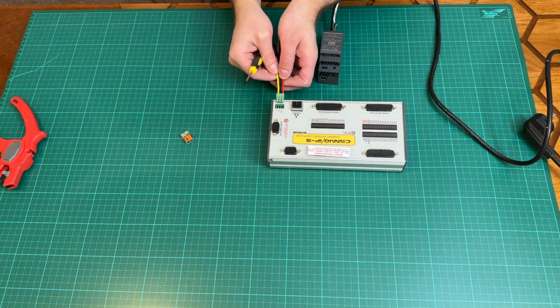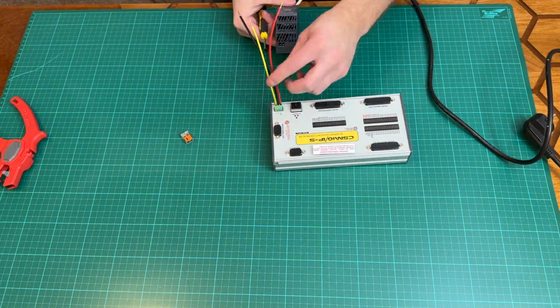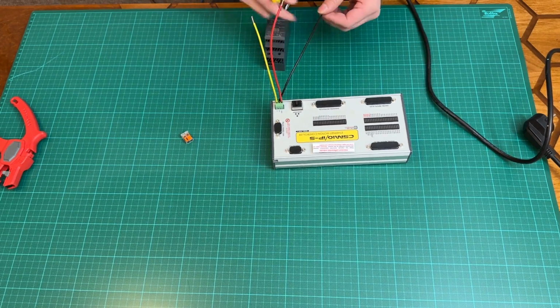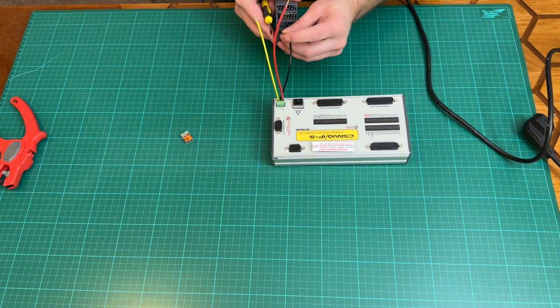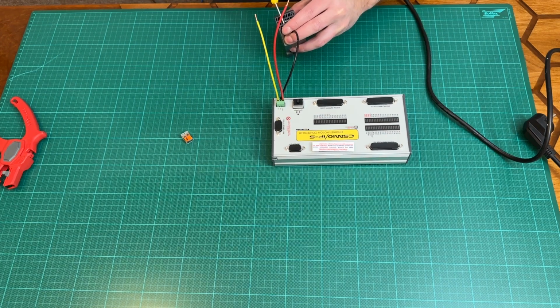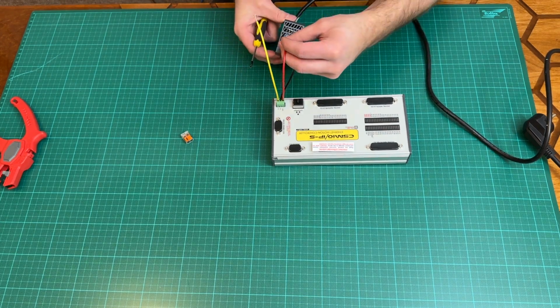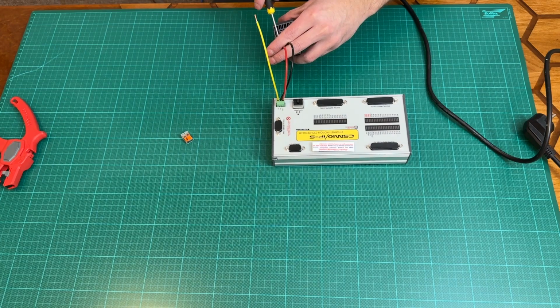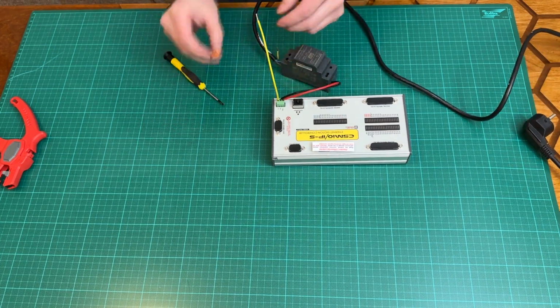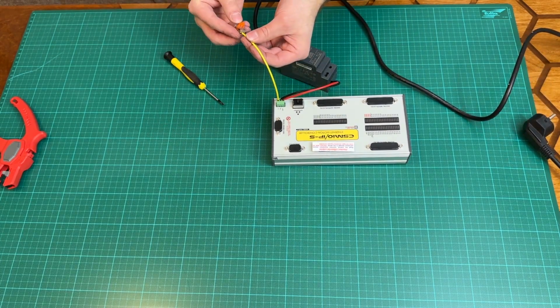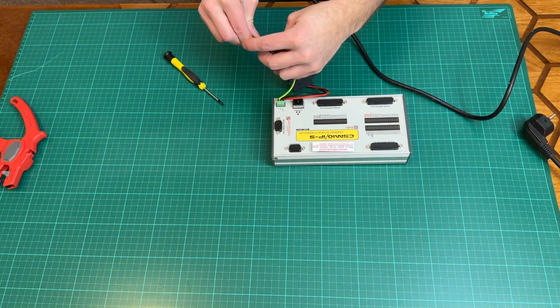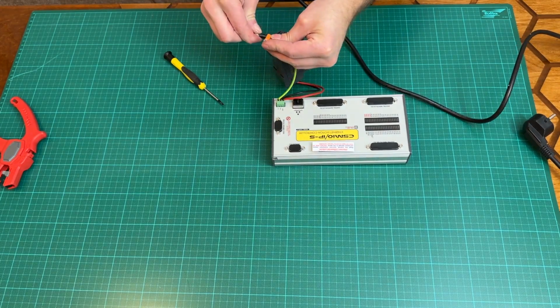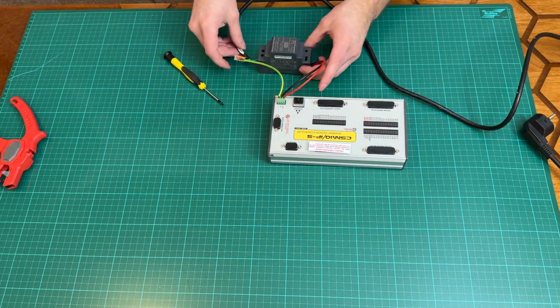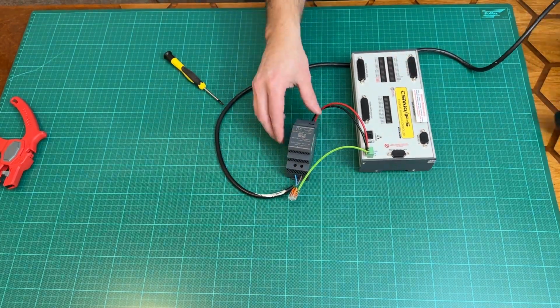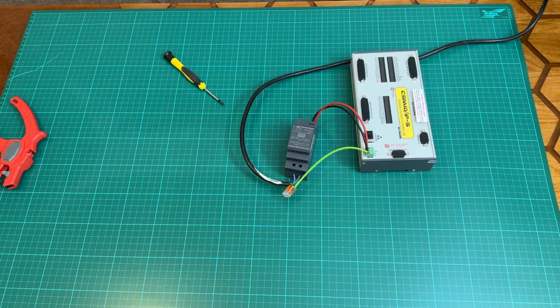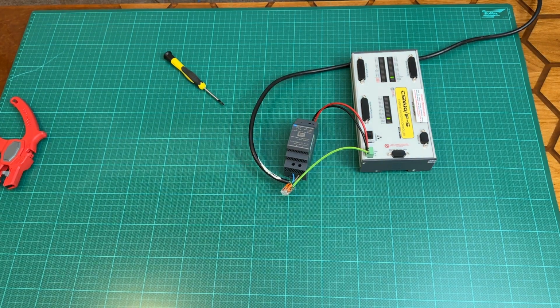Let's connect the 24-volt power supply to the controller. We're using a Meanwell 24V power supply, and here are the steps. Take the cable with the plug and connect the live, or hot, and neutral wires to the power supply. Leave the earth, ground wire disconnected for now. From the power supply, connect the 24 volts and ground wires to the controller. Finally, connect the earth wire from the controller directly to the main cable. That's it. You've successfully connected the power supply to the controller.